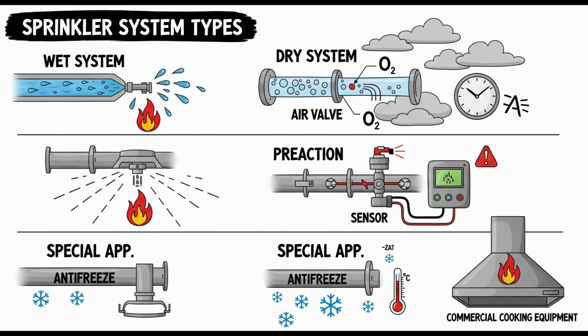Interesting alternative approach, a sort of shock absorber for pressure. Kind of, yeah. Can a wet pipe system feed other types of systems, like the more specialized ones? Yes, it absolutely can. A wet pipe system is permitted to supply water to smaller, auxiliary dry pipe, preaction, or deluge systems. The crucial caveat is that the overall water supply has to be sufficient to meet the demand of all systems it's feeding simultaneously under fire conditions. So the fundamental wet system can be the backbone for more specialized zones, provided the supply is big enough.